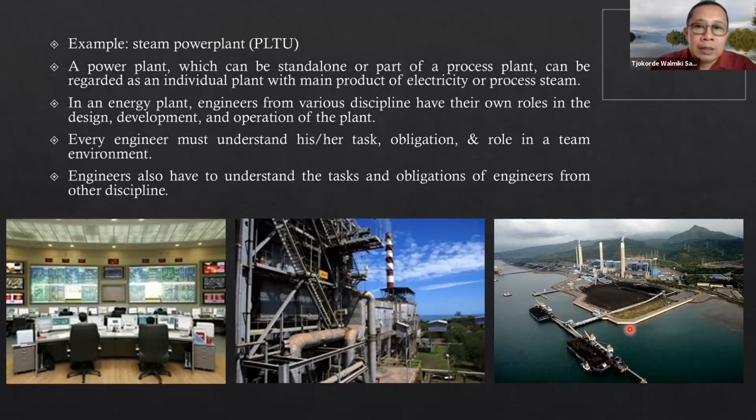Harus dibalik-balik. They use heavy equipment, peralatan berat, bulldozers or excavators, to turn this pile inside out. The point is to circulate air throughout the pile of coal to prevent thermal buildup, to prevent temperature increase, which if it becomes too high will ignite the interior of the pile, and that can be very dangerous.